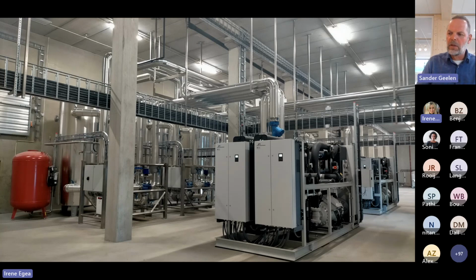And maybe some details about the heat pumps that were requested also in the chat. These are Combitherm heat pumps from Germany using Bitzer screw compressors. We are using refrigerant R1233ZDE. We have a source temperature flowing into the heat pumps of approximately 40 degrees Celsius, a little higher sometimes. And the sink in Norway is roughly 100 degrees max, but in Korea we are already at the sink of 120 and now upgrading to 130.